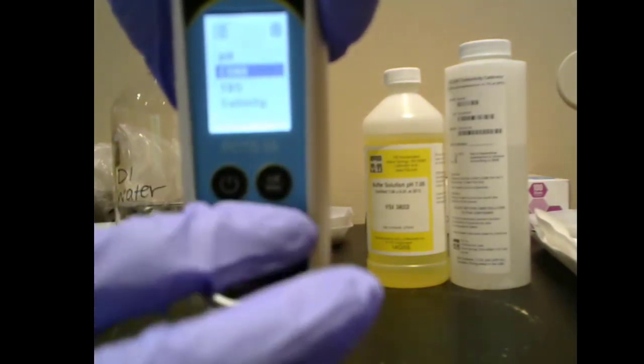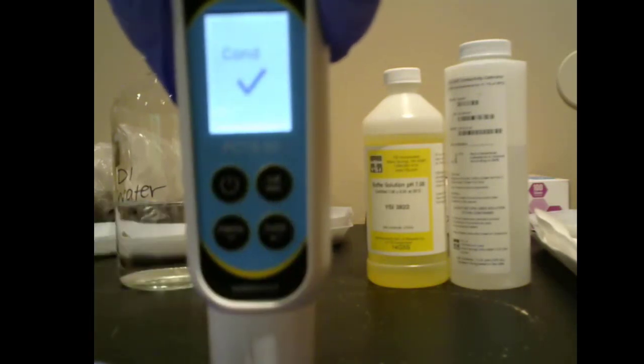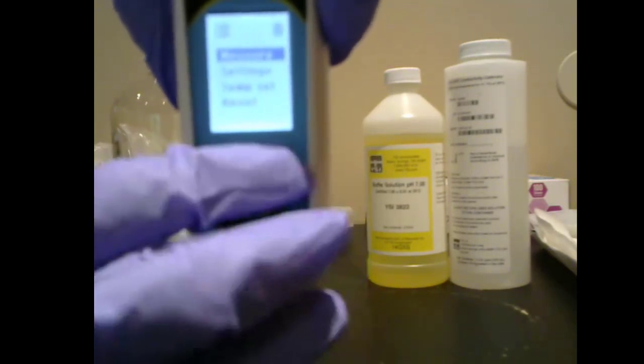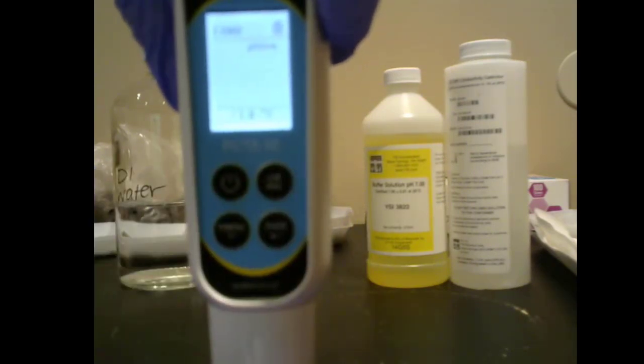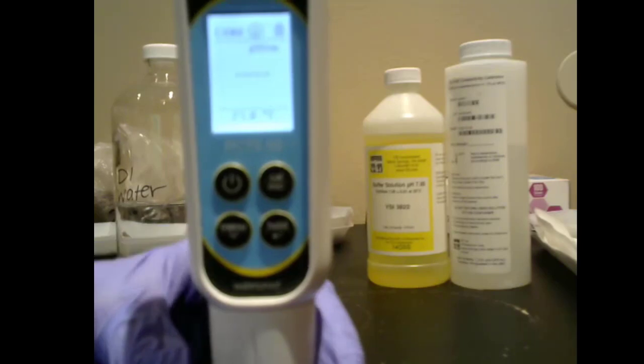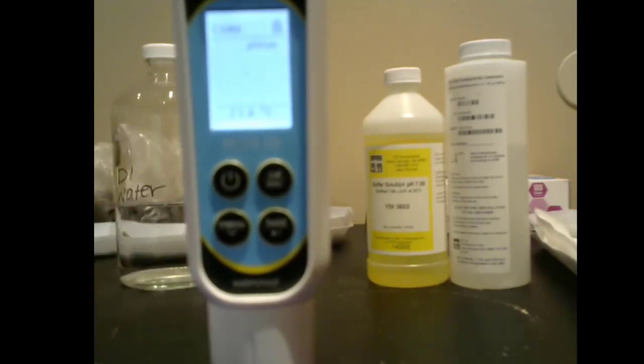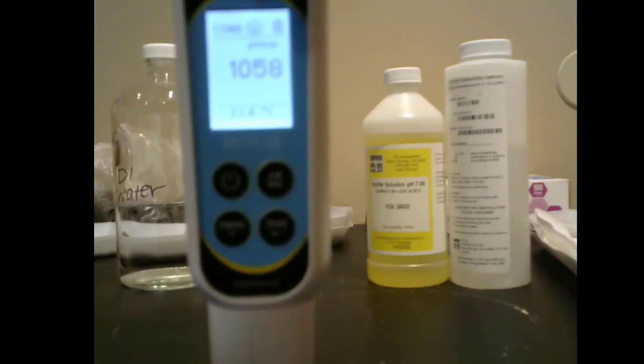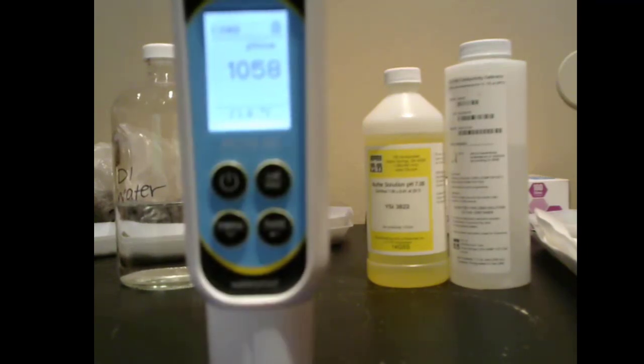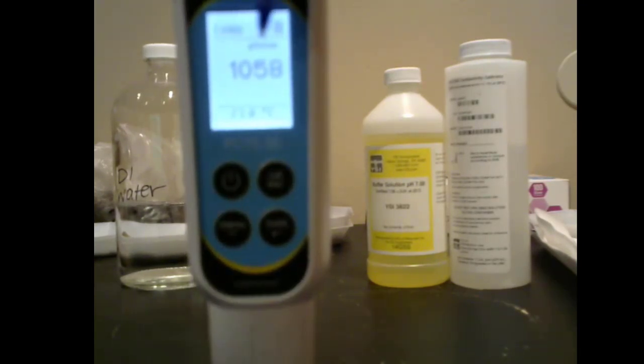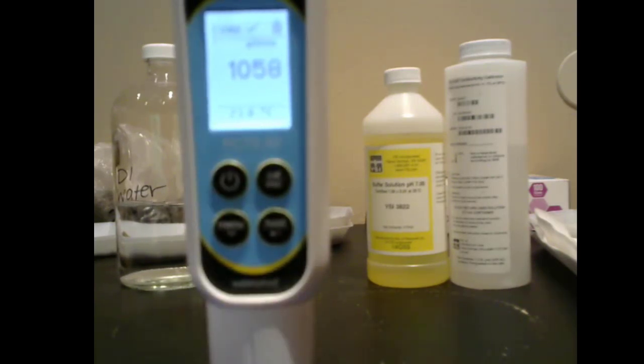So we're going to use menu to scroll down to conductivity, hold to select. Now we are in conductivity. Now we just need to push cal to escape back to our measurement window. And now we are back in our measurement window, and we're going to wait for our conductivity value to read and then stabilize. Okay, so now we have a reading, and you could see this clock again waiting for that reading to stabilize. Now if you could see a little more clearly, you would see right in this area the units are listed as microsiemens per centimeter.